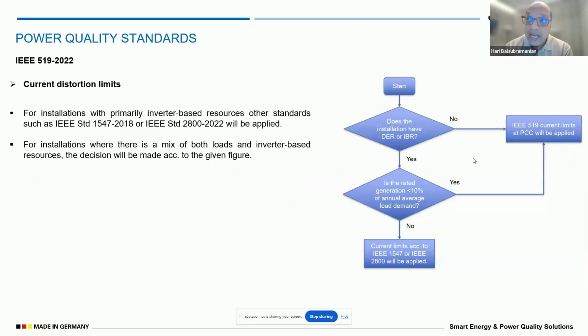Now, do I say that IEEE 519 is for all circuits, even if I have generation in my circuit? No, it very clearly says that if there is distributed generation greater than 10%, then other current limits need to be followed, like IEEE 1547 or 2800. But if the generation is less than 10% of the average load demand, then we need to follow IEEE 519. So there is also a classification. I say this because a lot of industries now have solar power generation as part of their system. If it is 10% and more at site, a different standard should be followed. If the solar generation is less than 10%, then IEEE 519 can very well be followed.